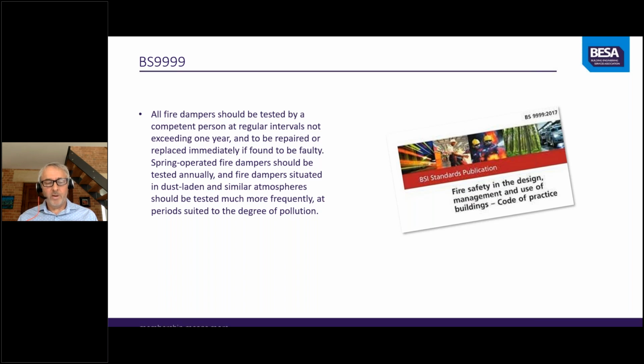Now, spring-operated fire dampers are commonly designed to activate when temperatures exceed the manufacturer's predetermined threshold, which is typically 72 degrees C, and the fusible link releases. The spring-loaded fire damper will then release and contain the fire and hot gases to prevent the spread of fire.